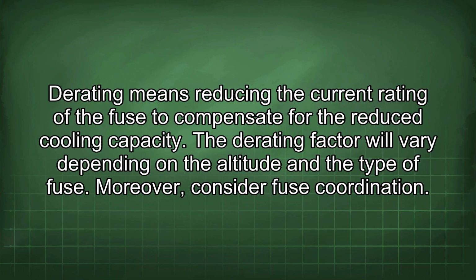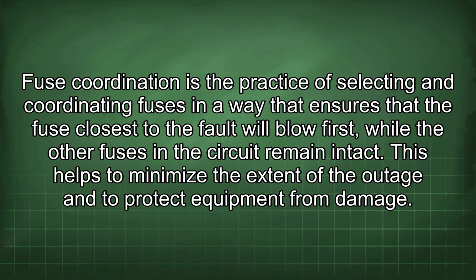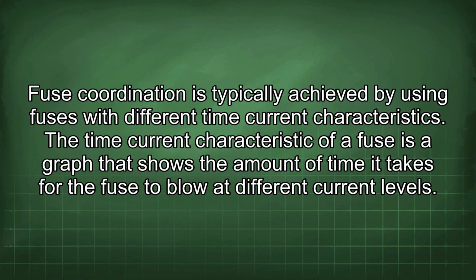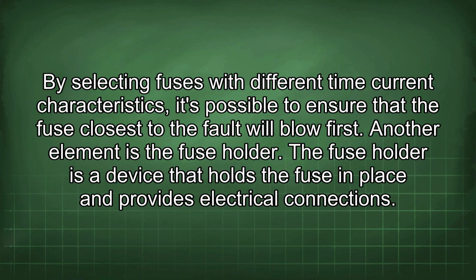Moreover, consider fuse coordination. Fuse coordination is the practice of selecting and coordinating fuses in a way that ensures that the fuse closest to the fault will blow first, while the other fuses in the circuit remain intact. This helps to minimize the extent of the outage and to protect equipment from damage. Fuse coordination is typically achieved by using fuses with different time current characteristics. The time current characteristic of a fuse is a graph that shows the amount of time it takes for the fuse to blow at different current levels. By selecting fuses with different time current characteristics, it's possible to ensure that the fuse closest to the fault will blow first.